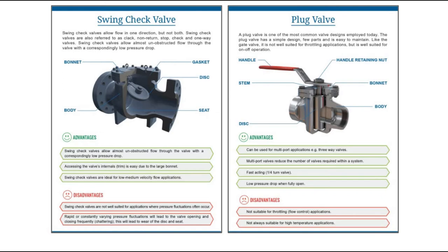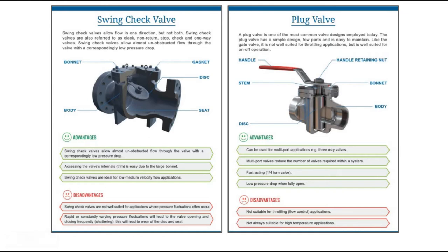The next valve types are swing check valve and plug valve. Swing check valves allow flow only in one direction. They are also referred to as clack valves, non-return valves, stop check valves, and one-way valves. Swing check valves allow almost unobstructed flow through the valve with a correspondingly low pressure drop. The different parts visible in the diagram include the disc, seat gasket, bonnet, and the body. Accessing the valve internals is easy due to the large bonnet, and swing check valves are ideal for low to medium velocity flow applications.